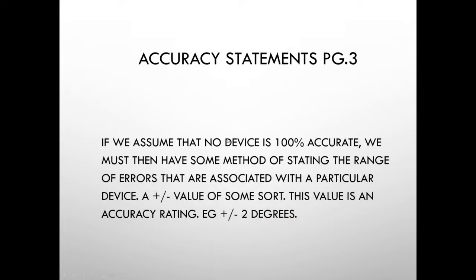When we talk about accuracy, we quantify it in something called an accuracy statement. We automatically assume no device is 100% accurate, so we must have some method of stating how inaccurate it is. This is done by stating the range of errors associated with a particular device — a plus or minus value of some sort, generally in some type of unit. We call that an accuracy rating. For a thermometer, it may be accurate to plus or minus two degrees of the reading, or two degrees of span.